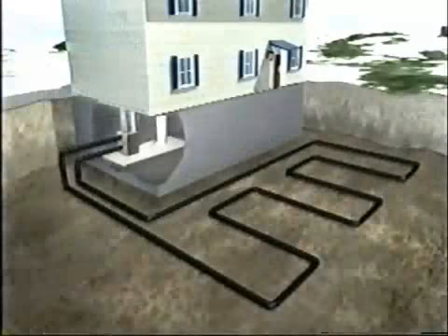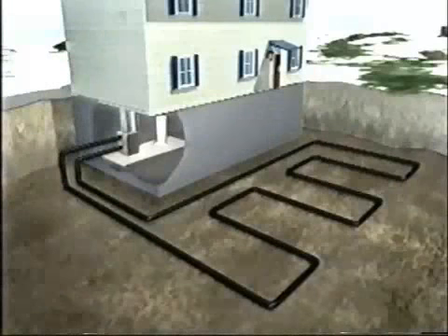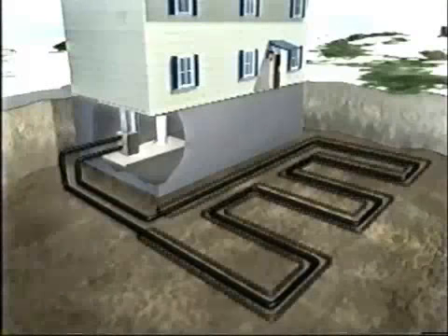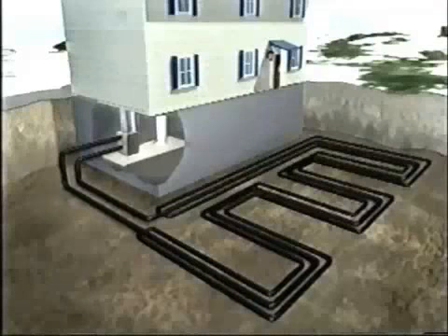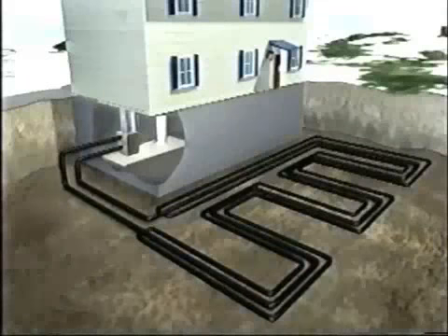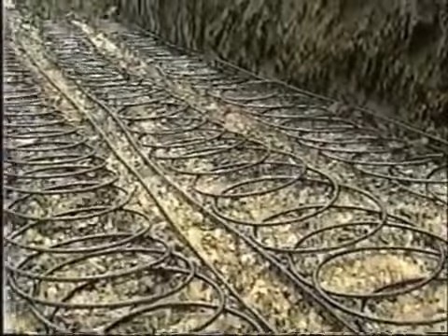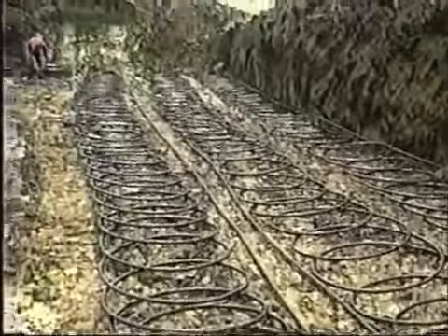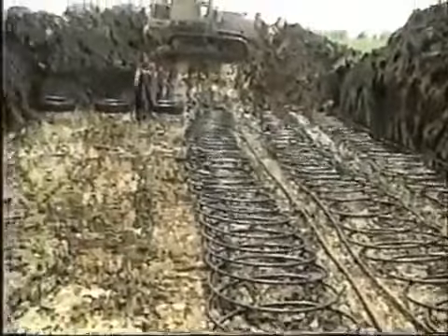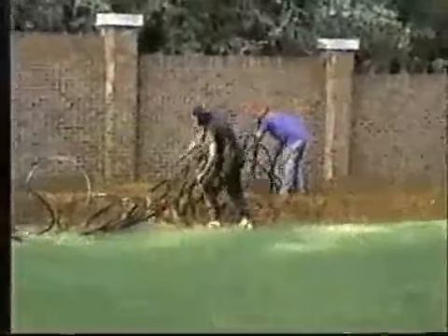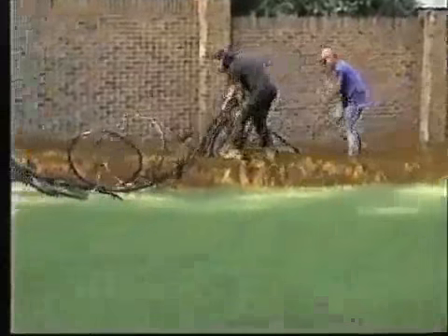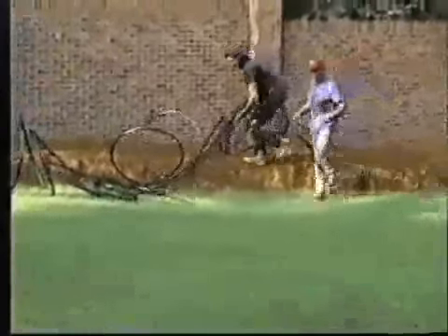In some installations, the pipes of a closed-loop system can be placed in a horizontal trench dug below the frost line. The number of pipes in each trench and the number of trenches needed will vary depending on the size of the geoexchange system being installed and the type of soil found in the area. To minimize trenching, slinky coils, spring-like coils of polyethylene pipe, can often be used to increase the pipe surface area and thus the heat exchange per foot of trench.